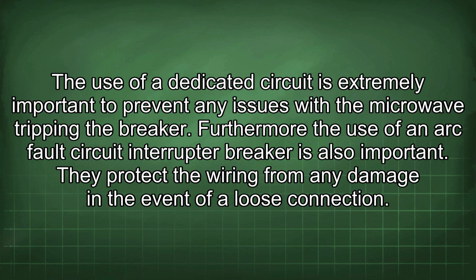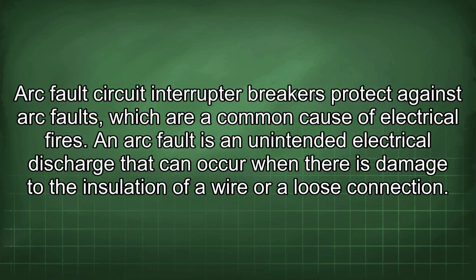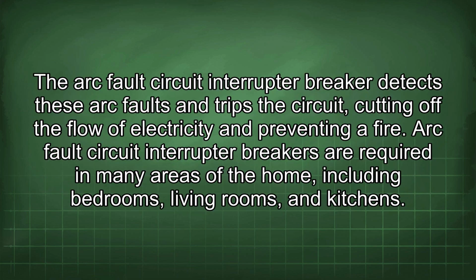The use of a dedicated circuit is extremely important to prevent any issues with the microwave tripping the breaker. Furthermore, the use of an arc fault circuit interrupter breaker is also important. They protect the wiring from any damage in the event of a loose connection. Arc fault circuit interrupter breakers protect against arc faults, which are a common cause of electrical fires. An arc fault is an unintended electrical discharge that can occur when there is damage to the insulation of a wire or a loose connection.